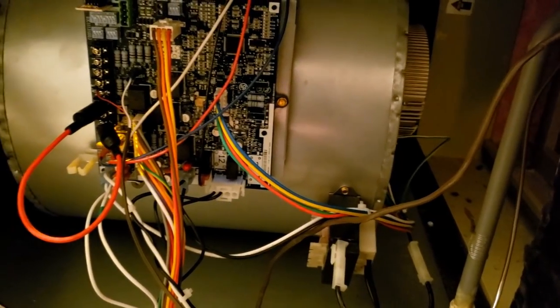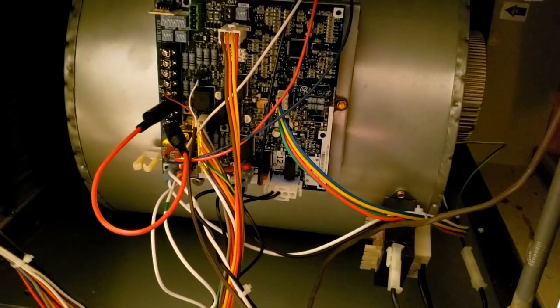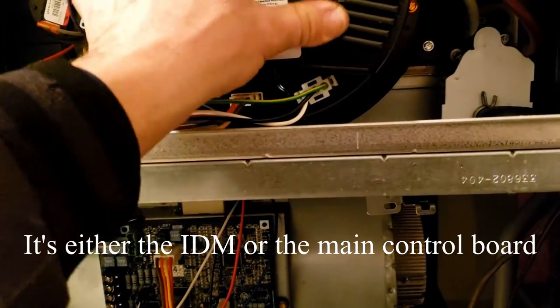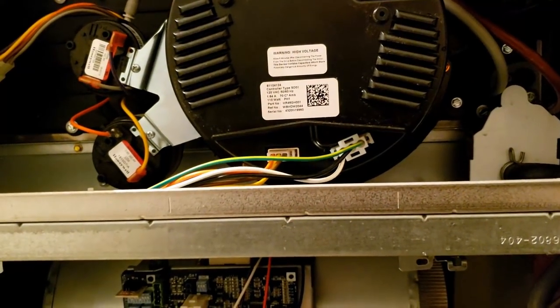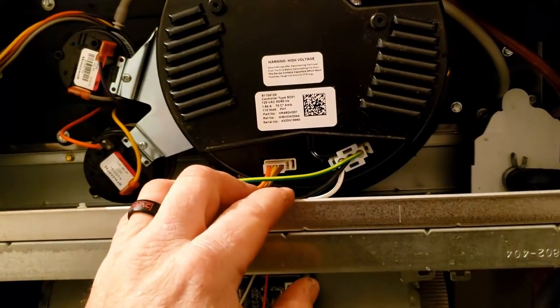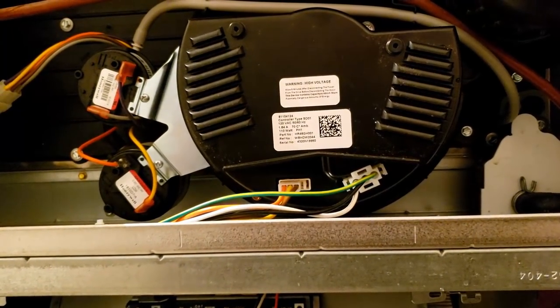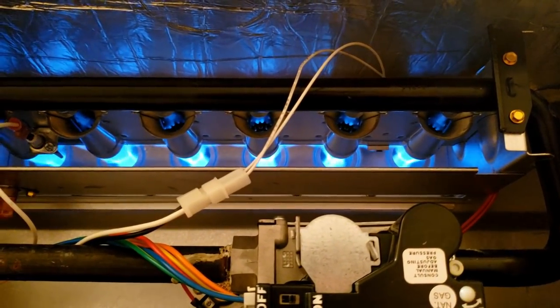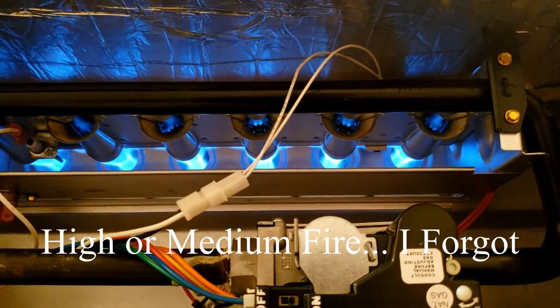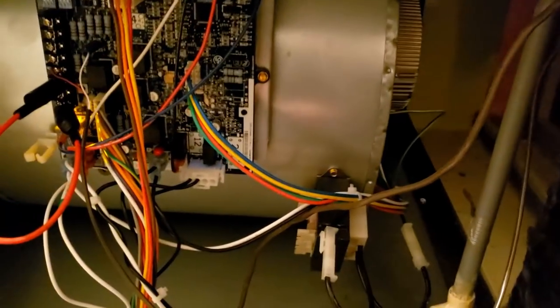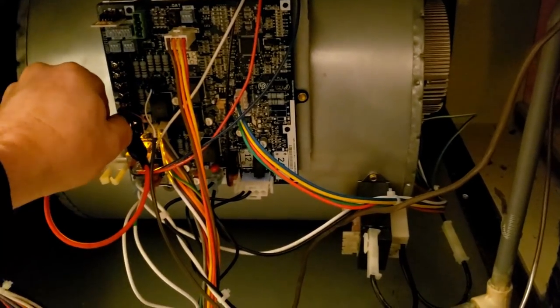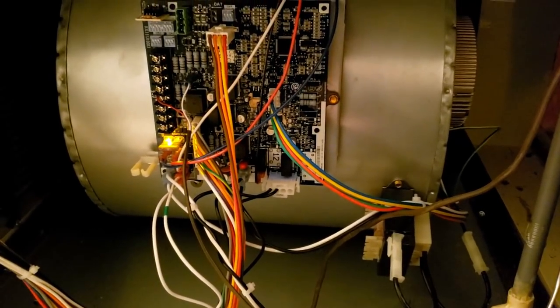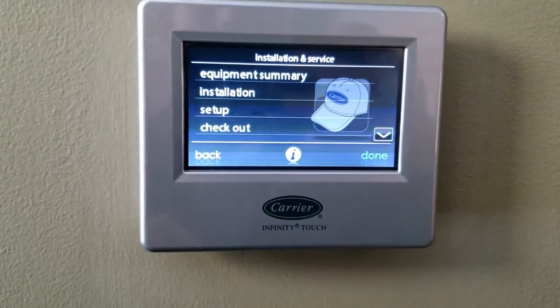So we'll go ahead and put it back on the controller. There's really not a lot - I mean, you can, like I said, you can go through the diagnostics of the motor here, which I'm going to make a copy for myself for later. But having that with you, it's pretty nice. Now you can see it's dropping down to the low position. You should always fire off about in a medium and then start ranging from there based off whatever it feels comfortable with. So there goes the blower. So we are on a roll, which is great. So we're going to go ahead and wire this thing back up for the controller.